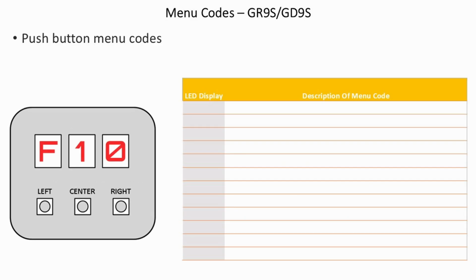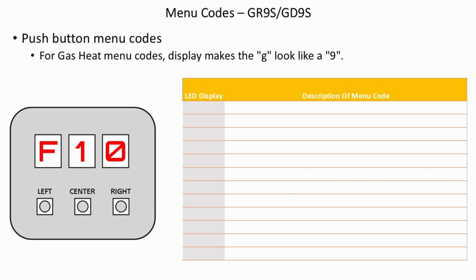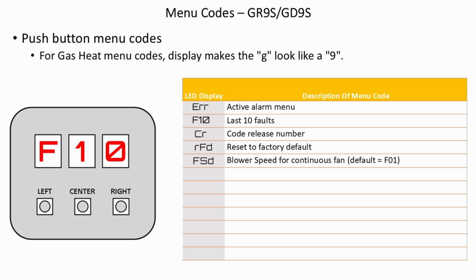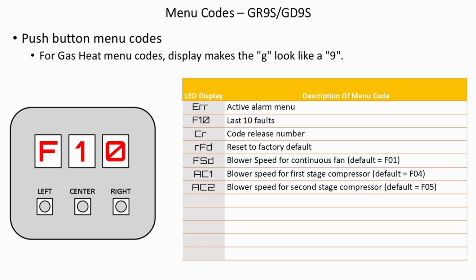Menu codes. Push button menu codes. For gas heat menu codes, display makes the G look like a 9. ERR, active alarm menu. F10, last 10 faults. CR, code release number. RFD, reset to factory default. FSD, blower speed for continuous fan, default F01. AC1, blower speed for first stage compressor, default F04. AC2, blower speed for second stage compressor, default F05.